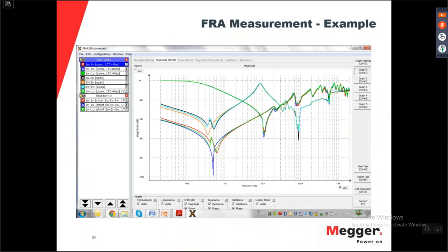So this is a typical measurement result that you will get. What you see is actually 9 measurements: 1, 2, 3, 4, 5, 6, 7, 8, 9. Where you have taken the measurement on each phase, phase A, phase B, and phase C, or H1, H2, H3, red, yellow, blue, whatever you would like to call them. But I'd say you have 3 phases in your transformer. And what you do is you measure each phase individually. And you measure it first, you measure the high side, phase A, phase B, and phase C.